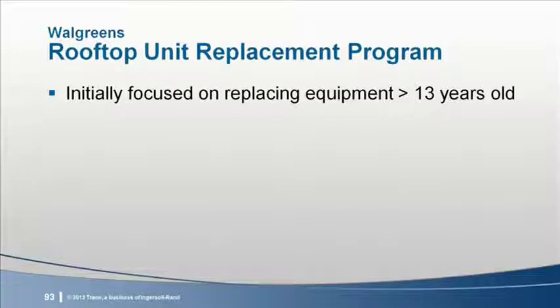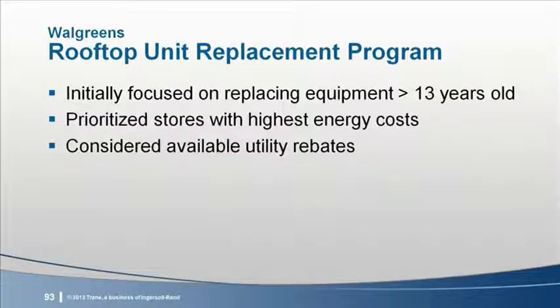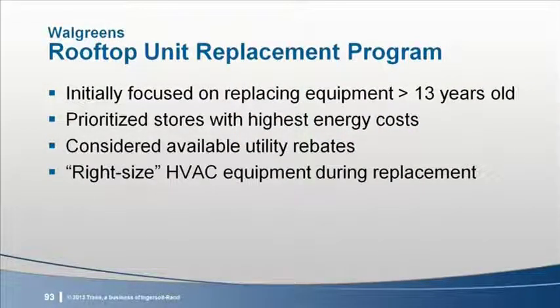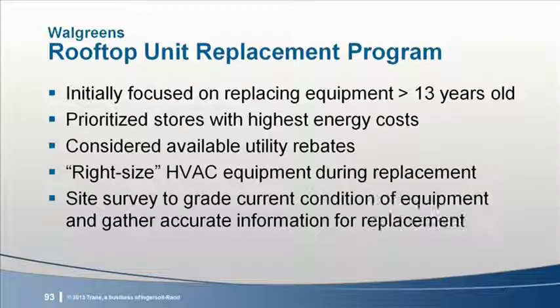Okay. So at the beginning, the criteria, we said, okay, every store that is 13 years or older, just to start somewhere, we're going to put it on the list, and we're going to go through different areas and concentrate on the highest energy cost, the highest utility rebates. And our engineering team, working with Nirmal, he came up with the idea. He said, hey guys, most of the stores are over-designed because the tonnage was much higher, which means increased running time. So we tried to review the design and the load, the CFM, and by the way, our retail business is about 14,000 square foot on average. So we found out that we can reduce an average of about 5 tons per store. That's a huge saving, in addition to an energy efficient unit, in addition to a brand new unit that you're going to balance very well. And the saving was amazing.